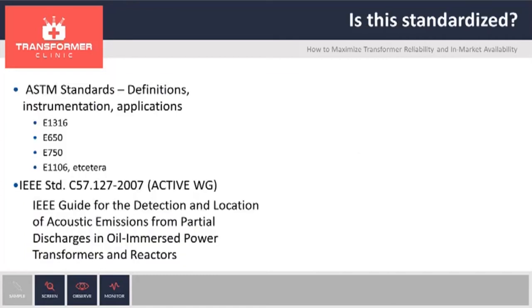This is normalized. We have ASTM standards that talk about frequency to be used, type of sensors, et cetera. But most importantly for us, we have an IEEE standard C57-127. This is an active standard. It's not a mandatory standard — it's just a guideline. Please note that this standard only talks about partial discharge. It doesn't talk about other types of defects that you can find. This standard is being reviewed, and we are part of that review committee.